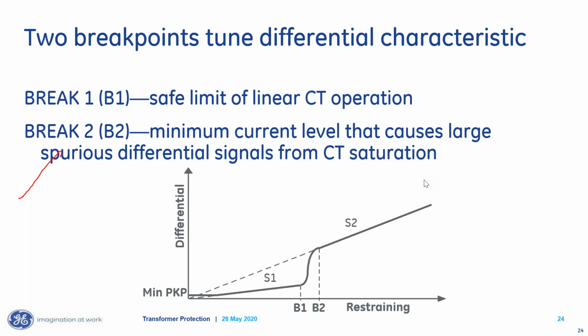But what that sounds like is you had some CT saturation on one of the sets of CTs, probably the lower voltage CTs on the transformer. This is assuming that the transformer relay was wired correctly, right? That also can cause a problem, but let's assume it is wired correctly. Then if it is CT saturation, the issue would be either the lower breakpoint setting or the lower slope setting. And again, it's possible that you had a wiring issue, or even that the relay wasn't set correctly.